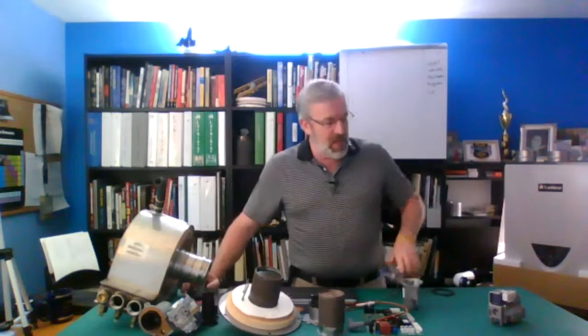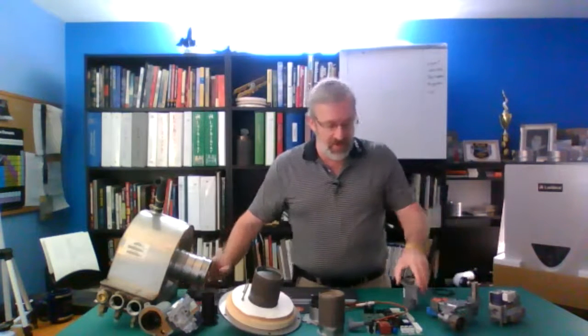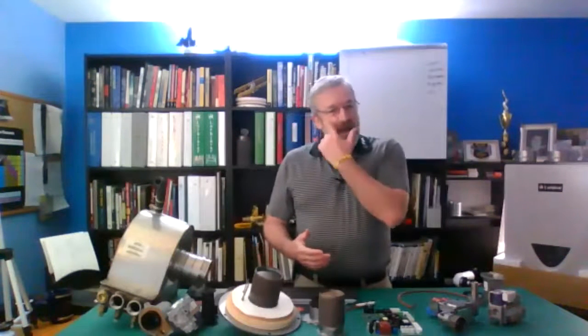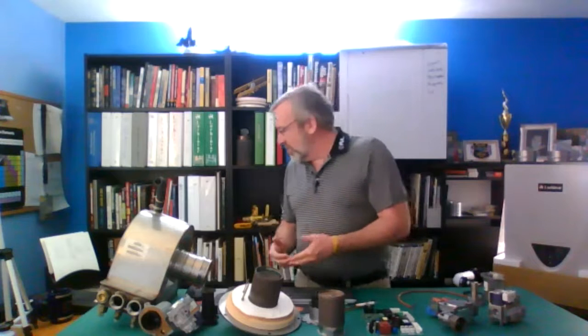So let's talk a little bit about the gas train and what goes through how this boiler works. Combustion-wise, on the boiler, we're looking at a negative regulation combustion system. Let me switch this one off here to try to clean up our internet a little bit. All right. In a negative regulation combustion system, what we have is a fan drawing air across a venturi.